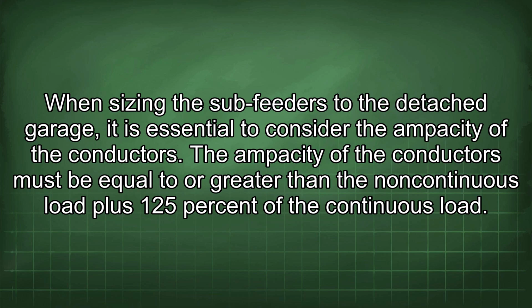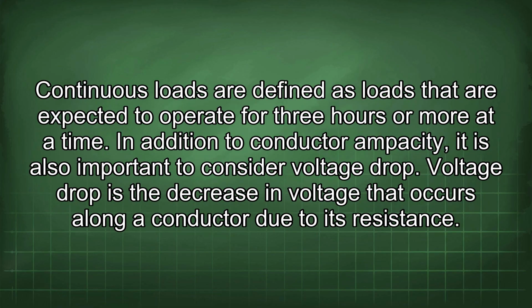When sizing the sub-feeders to the detached garage, it is essential to consider the ampacity of the conductors. The ampacity of the conductors must be equal to or greater than the non-continuous load plus 125% of the continuous load. Continuous loads are defined as loads that are expected to operate for 3 hours or more at a time.